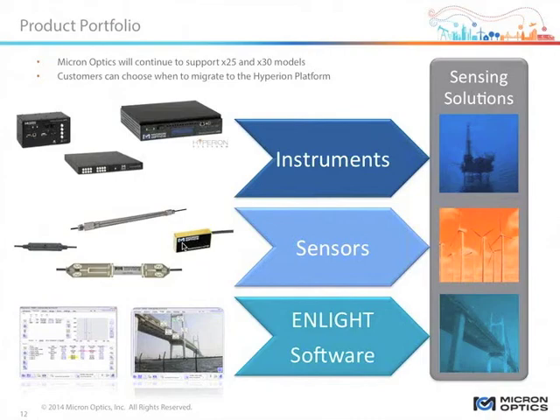What have you done in this design to improve? Okay, great question. To first order, the optical core of this interrogator, as I mentioned early on in this presentation, is an evolutionary design from that swept wavelength laser based upon our tunable filter, which has been in the field operating for an aggregate 100 million hours. And so when we look at our failures that have resulted in stoppage of operation, we can say unequivocally it's not been the laser. The laser really continues to function over time.